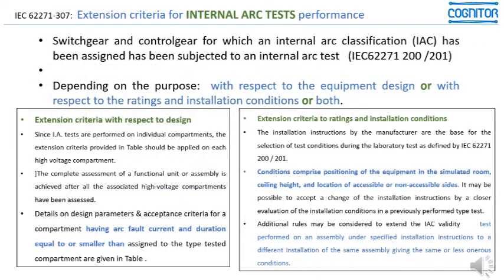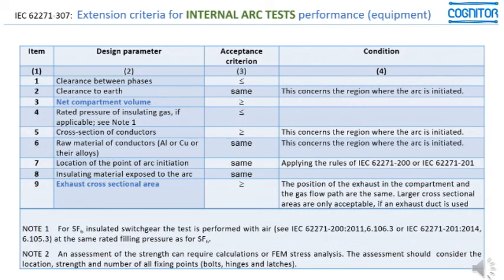The additional rules may be considered to extend validity for tests performed on an assembly under specified installation instructions to a different installation of the same assembly, given the same or less onerous conditions. This is an important opening, and it is not very difficult to verify if the essential criteria are met. Here you may see the design parameters and the acceptance criteria, and we have this list to check.